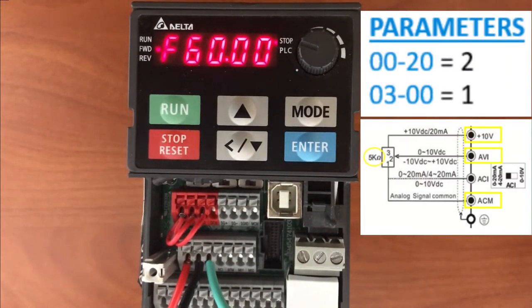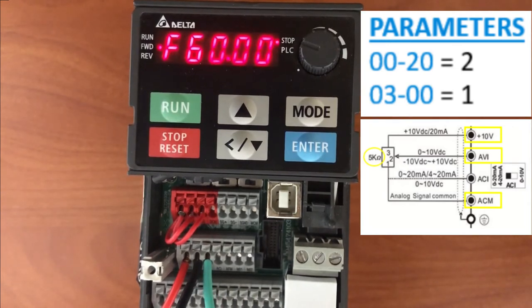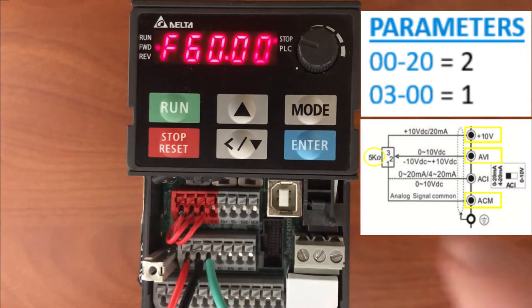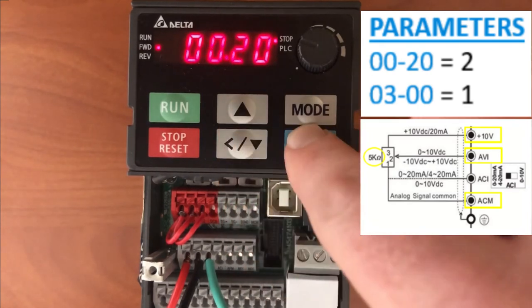I've got my drive set at factory default. I've got my plus 10 volts red wire, I've got my analog common black wire, and my blue is my AVI, my analog voltage input signal from my potentiometer. The drive is set at factory default, so I'm just going to go in and program these parameters.